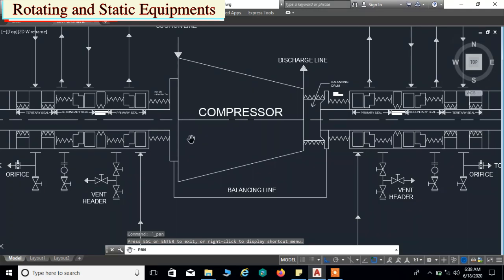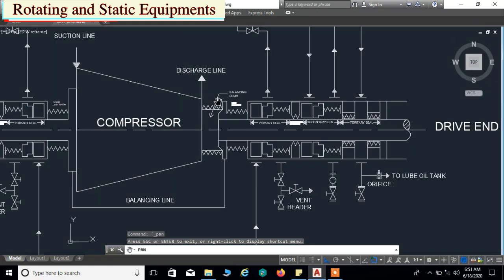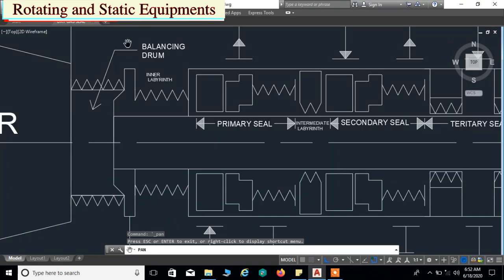Now we will see the internal components in detail. We will start from the drive end side. The compressor discharge gas which comes out between the balancing drum and the labyrinth enters into the chamber and returns to the compressor suction by means of an external connection called the balancing line. After the balancing drum we have the inner labyrinth in the chamber.